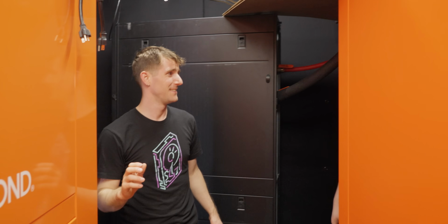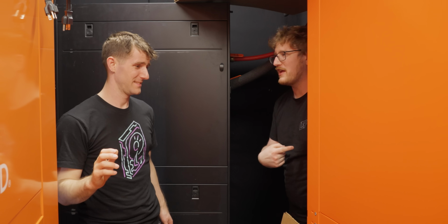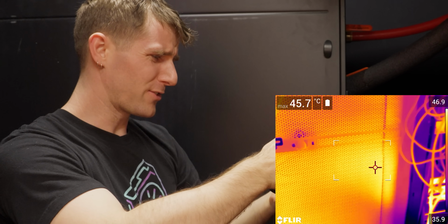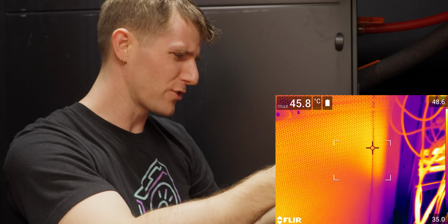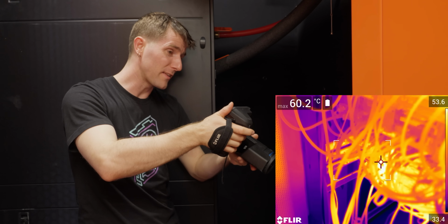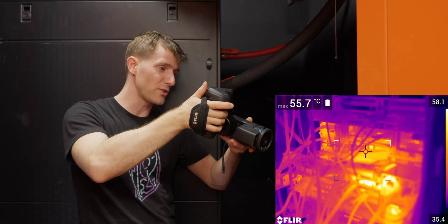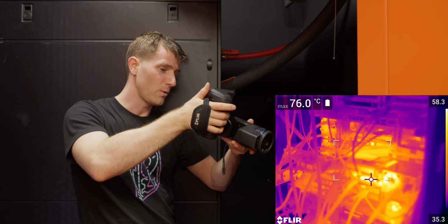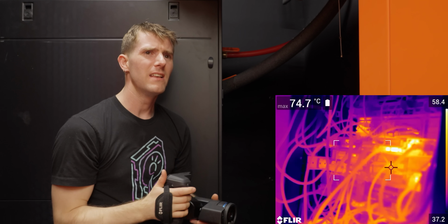Let's see what happens if we turn it off. Oh God, yeah, that is hot. I don't think the air conditioning is going to make that much of a difference in terms of the air coming out of here. The metal on the back of this rack is up to 46 degrees. The air coming out of the back of this power supply is as high as 60 degrees. Oh, 76. It's 33.2 now.